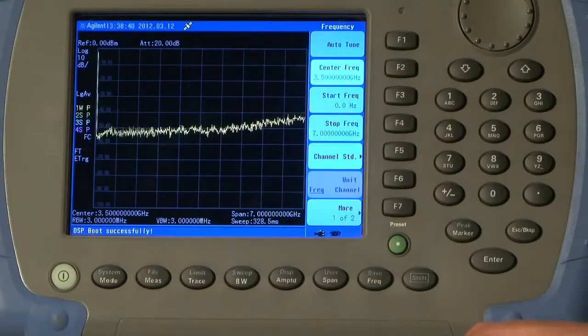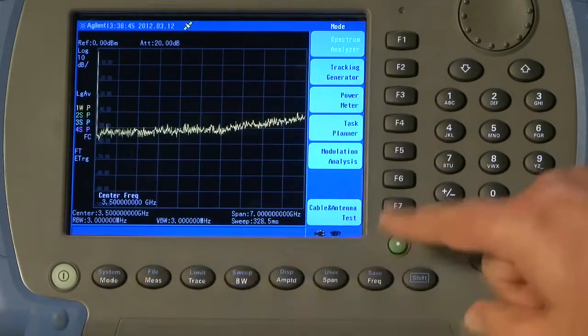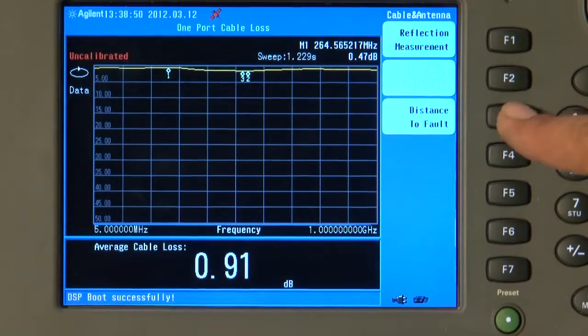Now let us make a distance to fault measurement of the same cable. With this we can identify the physical distance to cable breaks, cable damage, damaged connectors, water ingress and the like. So let us press the instrument preset button, mode, select cable and antenna test, and this time I am going to select the measurement of distance to fault.